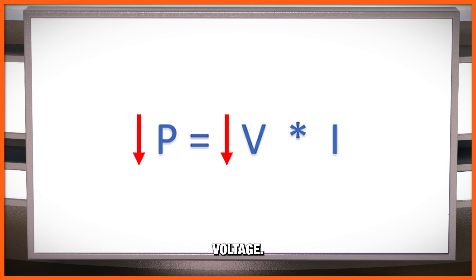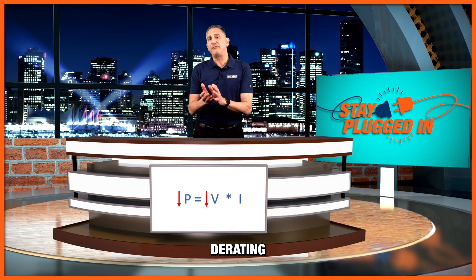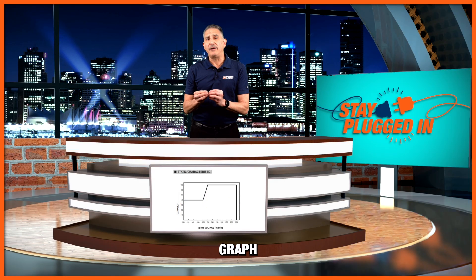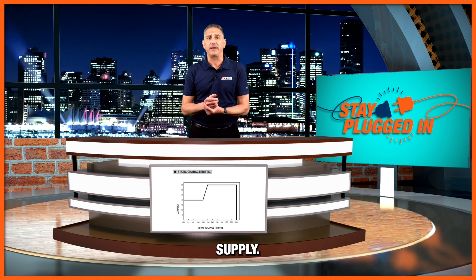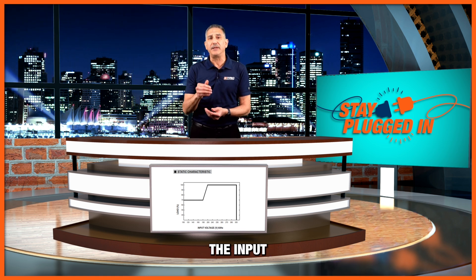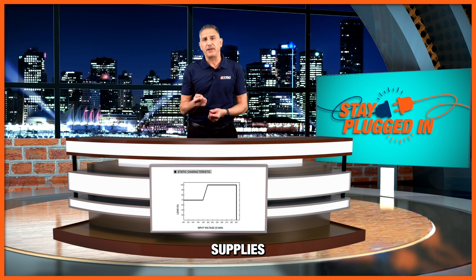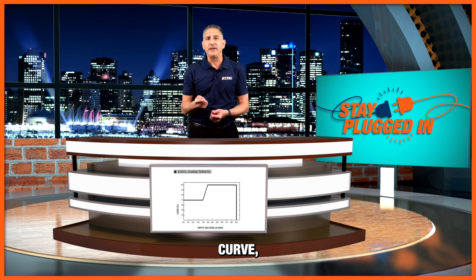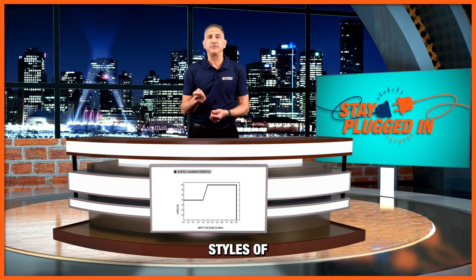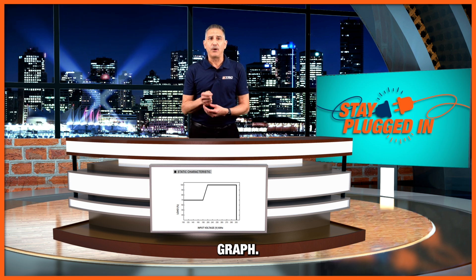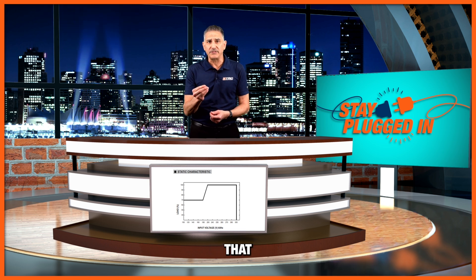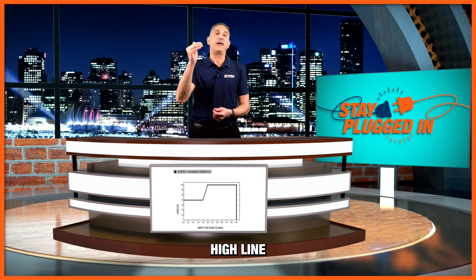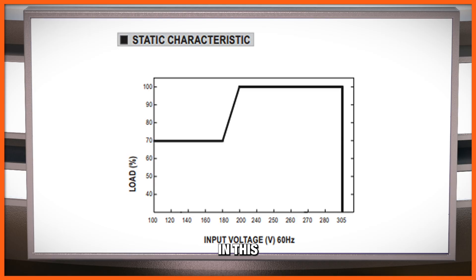An input derating curve is a graph that shows how you should reduce the maximum power output of your power supply depending on the input voltage. Many power supplies employ an input derating curve, and there are two common styles of this graph. One style has two distinct portions — flat portions that represent commonly used voltage ranges that we call high line and low line.